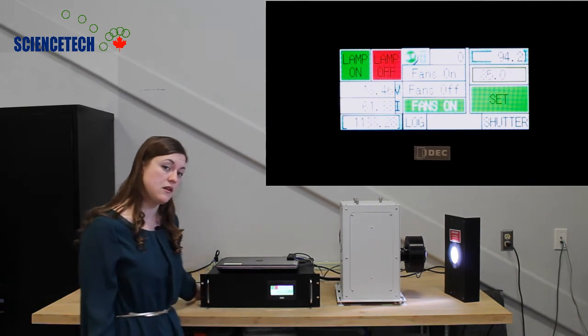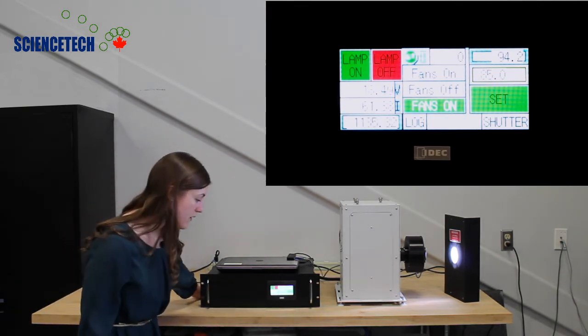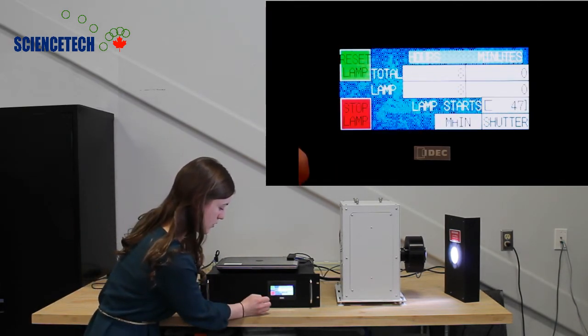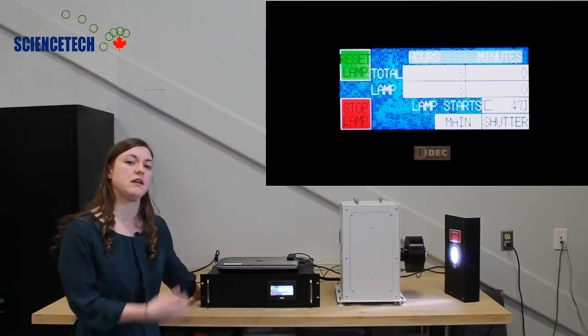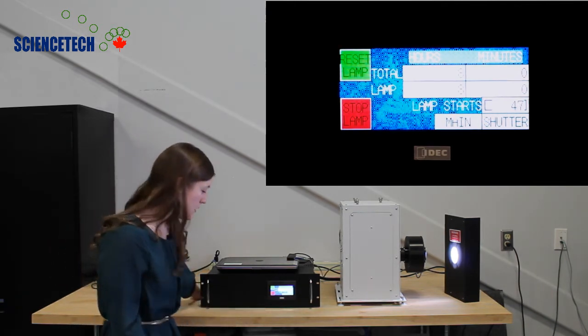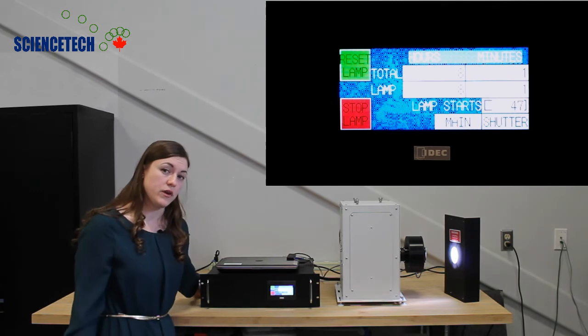It also has the ability to show you the log feature, which will tell you how long the lamp has been running, how many times it has been started, and you can reset it when you change the lamp.